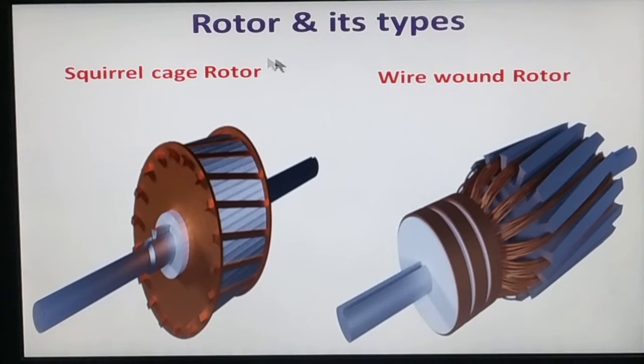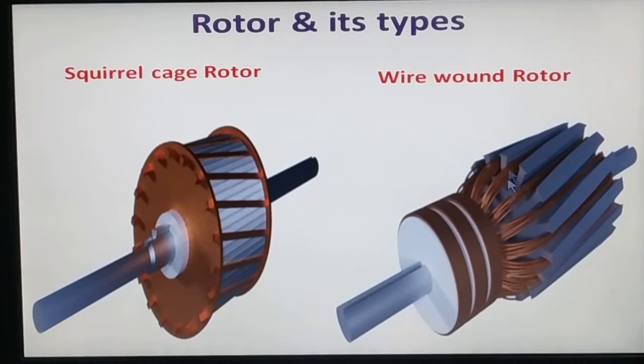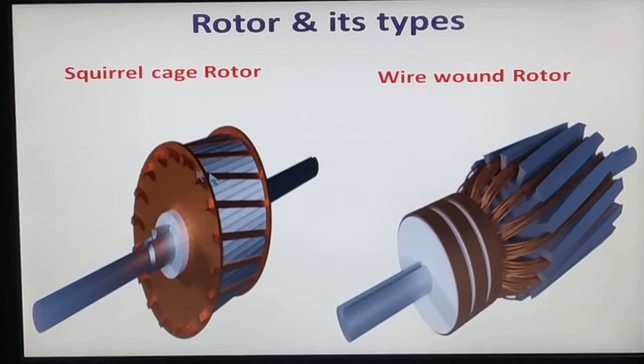The rotor is actually of two types: squirrel cage rotor and wound rotor. The difference is that the wound rotor has three-phase copper winding in the rotor slots, while the squirrel cage rotor has copper or aluminum bars inserted in the slots instead of winding. The bars can be straight or skewed — skewed means the bars are inserted at an inclined angle to the shaft. The skewing of conductors reduces the humming effect and magnetic locking effect.